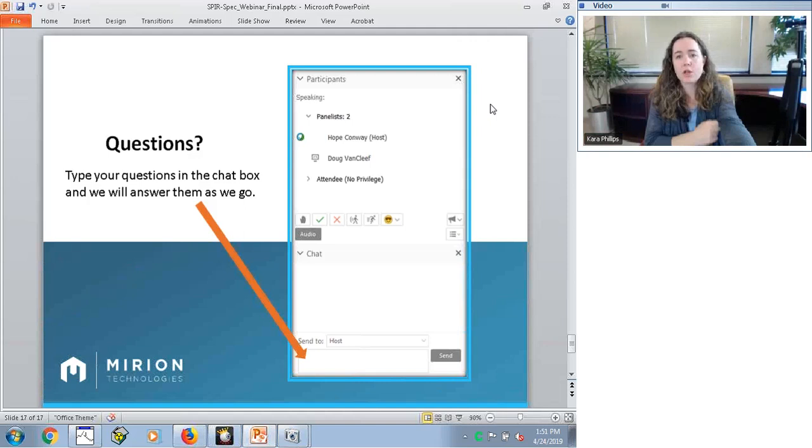Another question we have here is about how the background subtraction works. That's another very good question. So the background subtraction, the user actually has the option to have that both be enabled or disabled. In the case when it's enabled, the first step is just after a gain calibration or whenever beginning a measurement campaign, you'll initiate a background count here. And the background count then gets applied to the active measurement. So it'll always be the background that's going to be used until the user goes ahead and defines a new one to be done.